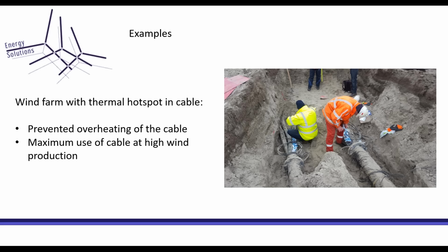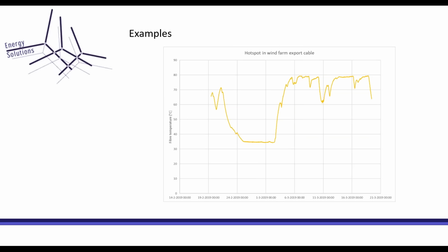This is a very recent example of a wind farm with 2 cables. The online monitoring system that was installed saw that there was a thermal problem on both of the cables, and it was found out that it was due to a very unfavorable thermal resistivity of the soil. It was completely dried out. And that's prevented quite a big fault in both of the cables. And at the moment they can use it to limit the production to the maximum temperature. So this is just a recent example of what it looks like.